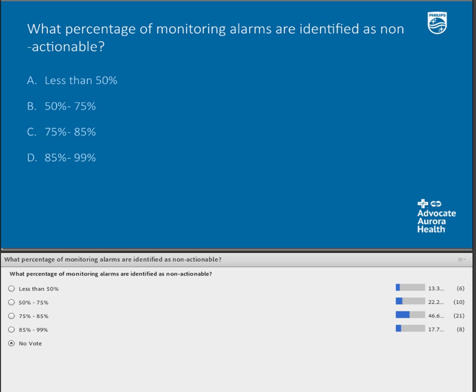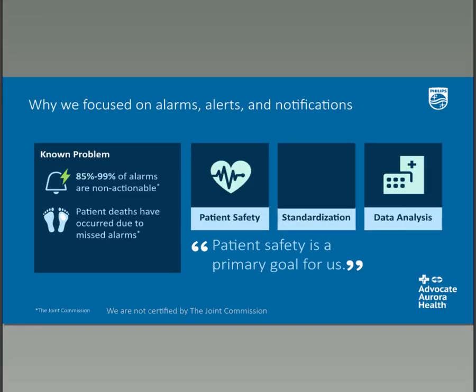The top answer that people chose was 75% to 85%. That's a pretty big number of alarms that would be non-actionable. However, the answer is actually 85% to 99% of alarms are non-actionable. That is a huge statistic, and this comes from the Joint Commission. Also from the Joint Commission, there have been patient deaths that have occurred due to missed alarms. These statistics are not from our hospitals specifically, but within our organization we have certainly had many concerns that alarms seem to go off all the time.